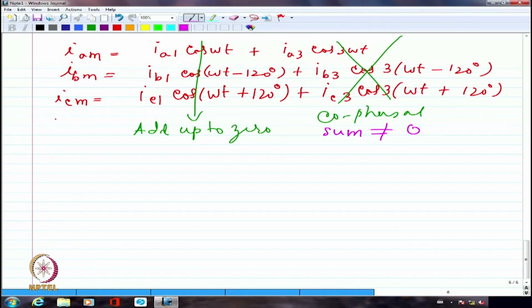That magnetizing current is going to always have harmonic components, and especially third harmonic is not going to find a path for itself to flow, because if I try to look at the neutral current it will have a non-zero third harmonic component. And there is no path for the neutral current. So where will the current flow? It cannot flow anywhere. If the current cannot flow anywhere, it has to cease to exist. It has to kill itself. There is no other way. So the current has to be primarily sinusoidal. It may have fifth harmonic, seventh harmonic, but those are minuscule as compared to third harmonic.